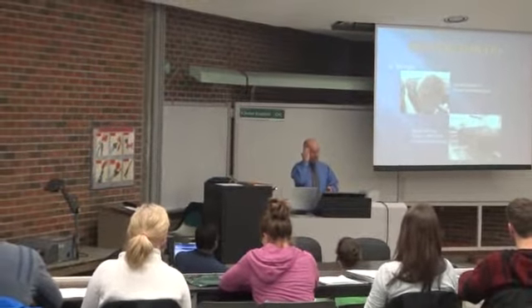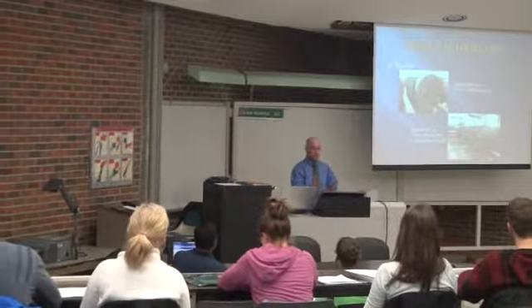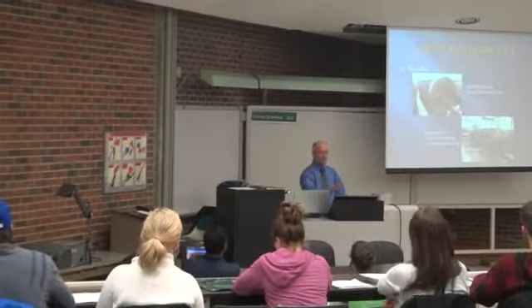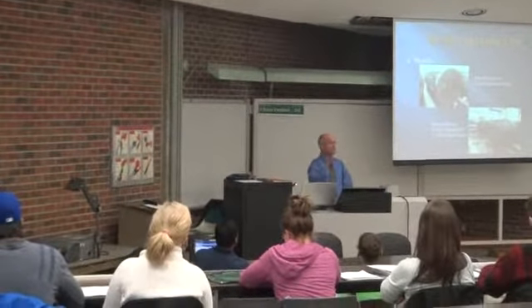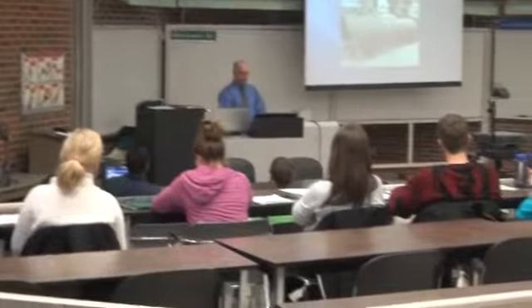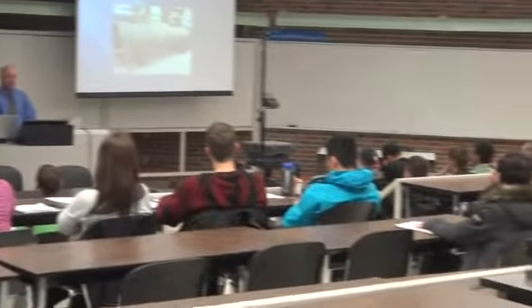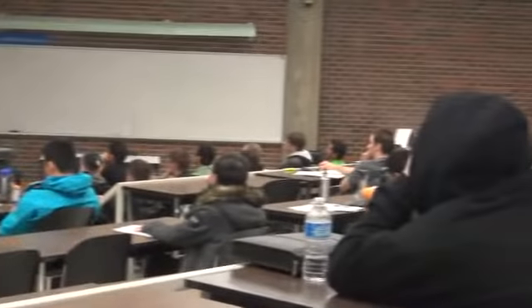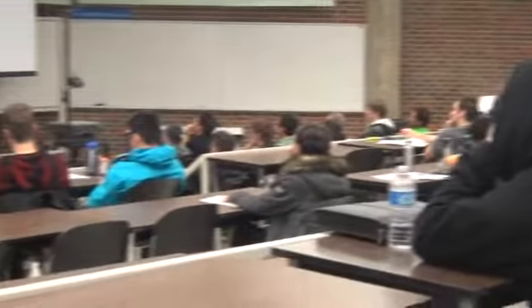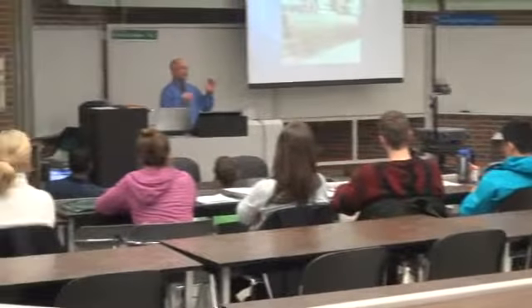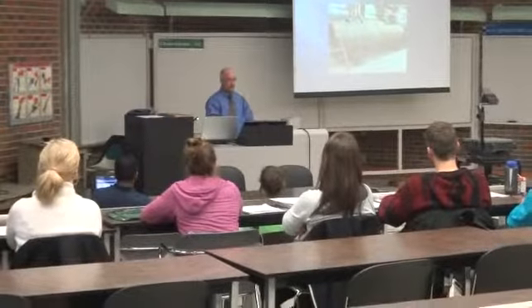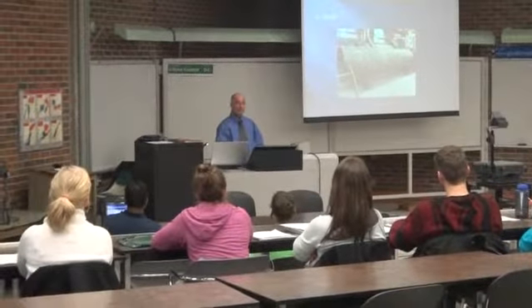The bottom right picture is the U-bend, and in this particular type of bundle, that's how the tube side fluid gets back to the front. This is a shell. There's no magic to this. This is a pressure vessel. So anybody that's worked with pressure vessels before, this is a typical pressure vessel. You've got a number of cylindrical shells that are all welded together, and then you'll either put a head or a flange on each end, and then you stab your bundle in it with your channel on.